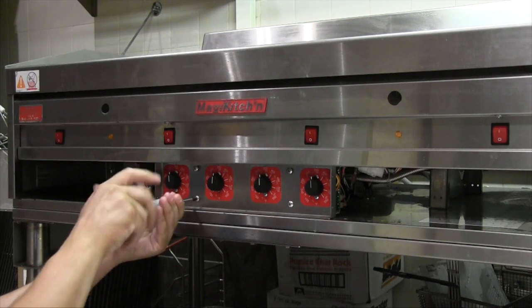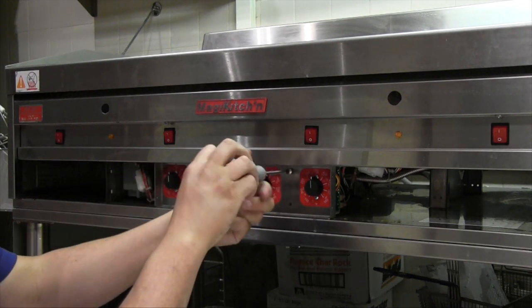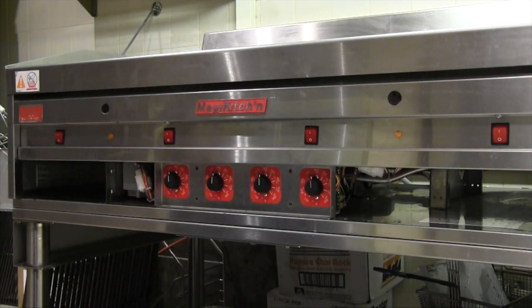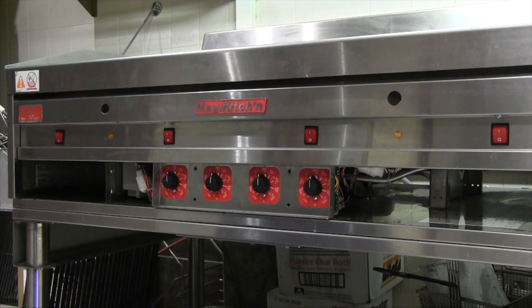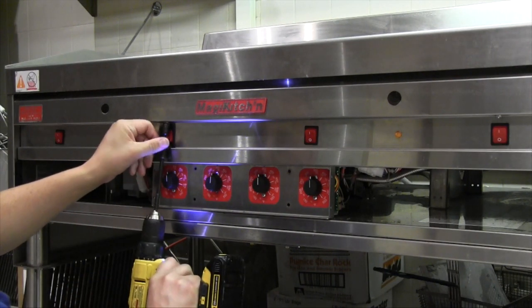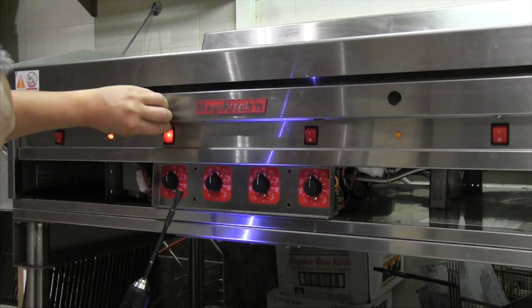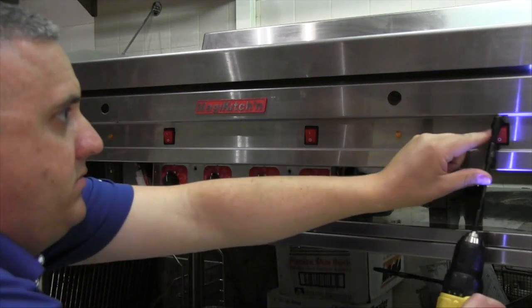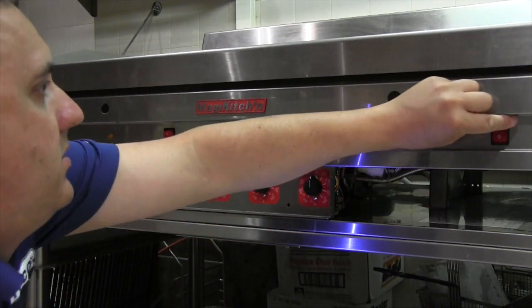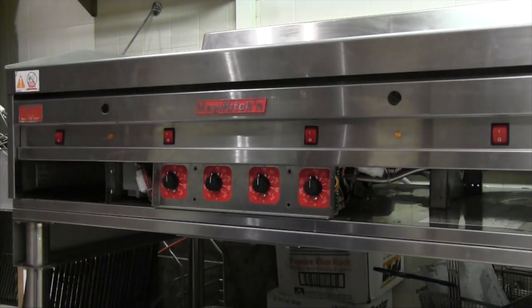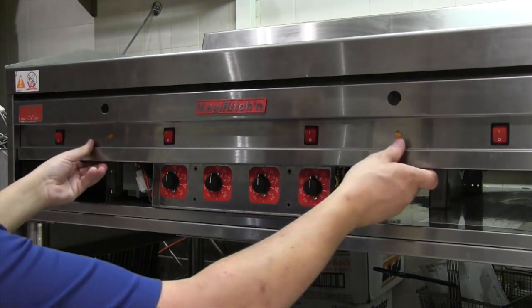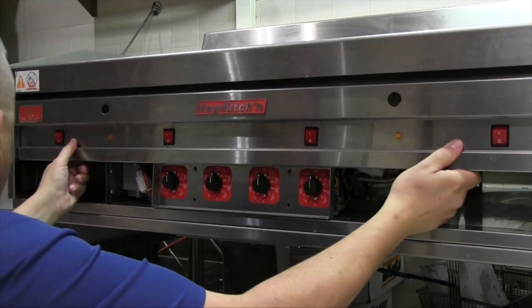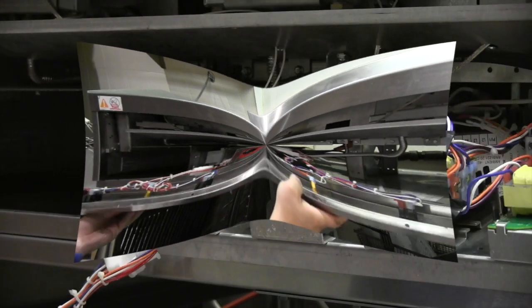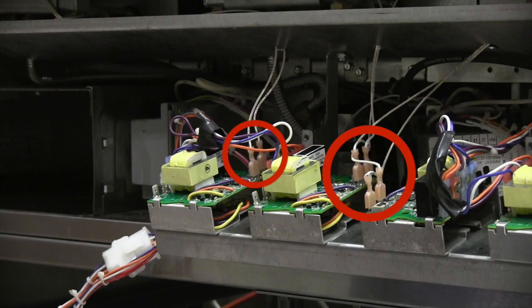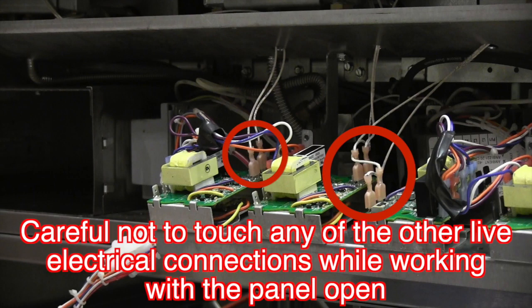Next, remove the 4 screws that hold the control panel in place. Remove the 4 5/16" screws that hold the front panel on and carefully lower the panel. Careful not to damage any of the wiring, lights, or switches in the process. Locate the temp probe wires going to the back side of the solid state controls. These should be light brown colored wires with female spade connections at the controls. 2 wires per control.